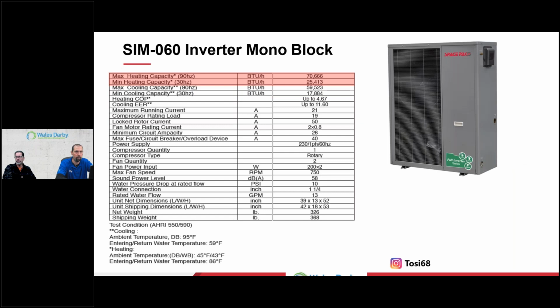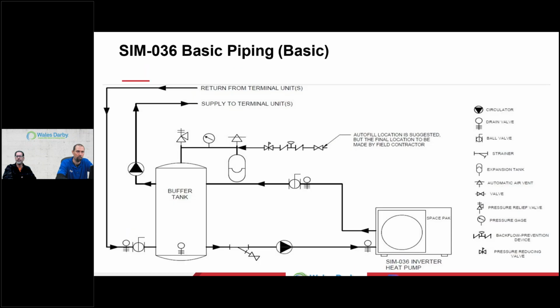Right. Here's the 60 or the 5 ton. Again, you can see that higher up the BTUs, upwards of 70,666 BTUs. Again, COP here is only upwards of 4.67, but the reality is at what testing parameters. Now apply that to reality in everyday living, and now maybe you back down into the 2s, again, 2 to 3 COP or 200 to 300% efficient, all right? Again, lowering water temperature, high efficiency. So this is what it looks like if you want to break it down.